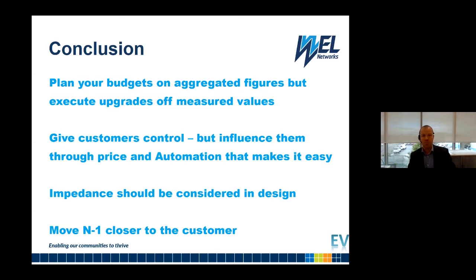We should be considering impedance in our design. So when suggesting an upgrade, look at the impedance, don't just make the smallest jump. Maybe the best solution to meet 2 or 3 EVs in the future is to chop the LV line and put in a new transformer. And the last point is to consider moving the N-1 closer to the customer.